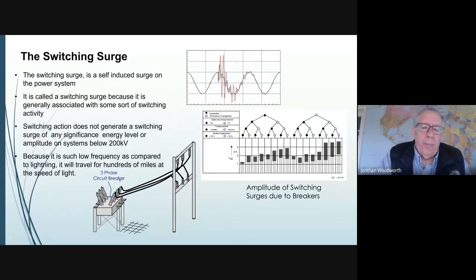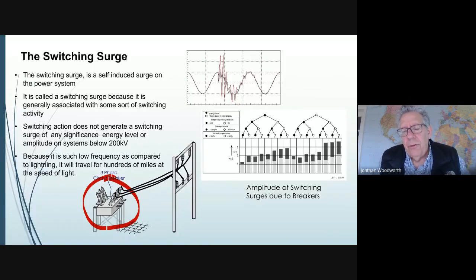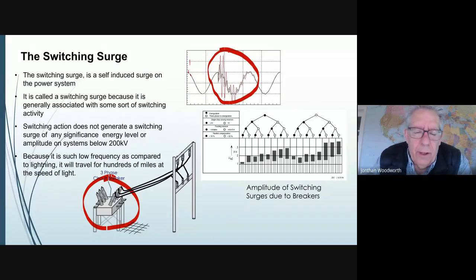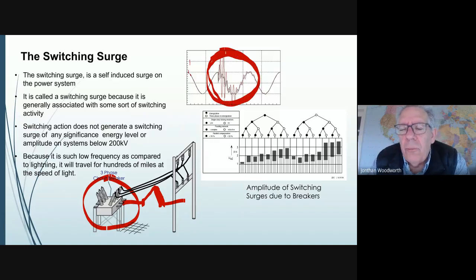There's one other surge that's caused by breakers. It's called a switching surge, and it's quite different from the lightning surge. One difference is that it's a very low frequency, whereas a lightning surge is just a very small blip on the line, say 40, 50, or 100 microseconds. A switching surge can last for cycles, because as the breaker contacts inside a breaker close, sometimes they spark over or arc over between the contacts. We try to make this as fast as we can so it reduces the surge, but almost always there's some sort of surge depending on where you close the switch, whether you close it at peak or at 0 volts. There's some kind of surge on the system, and this surge can be high enough, in some cases, to cause the insulators to flash over. So we spend a lot of time and effort to make sure that switching surges also do not cause flashover in systems.